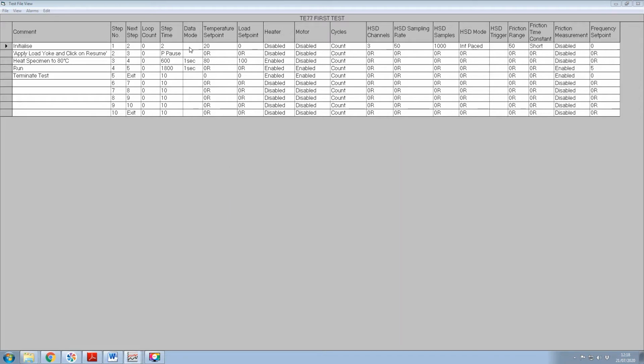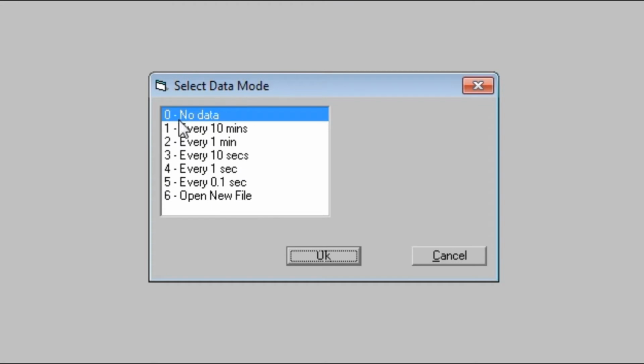Clicking on the step time box opens a parameter window. In this case, the selected step time is 2 seconds. The data mode column shows the data rate programmed for a given step. Clicking on the box opens a parameter box. The maximum data rate for low-speed data is once every 0.1 seconds, in other words, a 10 Hz sampling rate. There is also the facility to program opening of a new data file during a test. Data files cannot be viewed when they are being written to, so if you are running a very long test and want to view blocks of data while the test is still running, opening a new data file and closing the previous file will allow the latter to be opened and viewed.